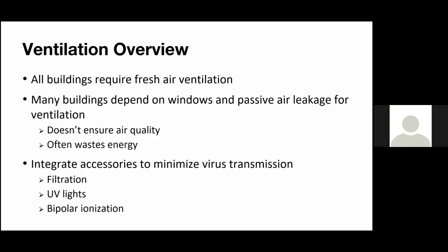So if you did want to install UV lights in your ductwork, maybe your return ductwork, right before you hit that mixed air, you can do that, or you could do it more in a centralized location. Maybe if you have a large DOAS system dealing with all your ventilation air, maybe you put UV lights in that DOAS or in that return duct before it goes back out, or before it hits the wheel.